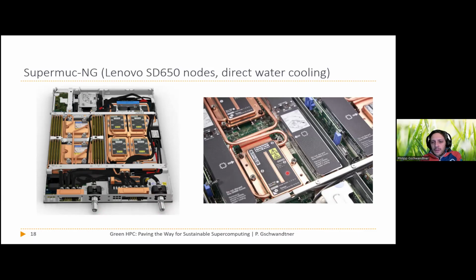The limits here are fairly high. On the right, it's a little small and I don't have a presenter that lets me zoom in, but we see star-shaped indicators with numbers showing the order in which the screws of the cooling plates have to be tightened. There are four screws, and they need to be installed in a very specific order.